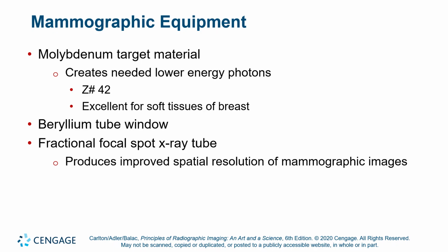Okay. If we use molybdenum as a target material, we're going to get lower energy X-ray photons out of a molybdenum target. Now, for X-rays of soft tissues like mammography, breast tissue, the molybdenum target is perfect for mammographic units. And so mammographic equipment has specialized X-ray tubes with different target material in the anode. They swap out the tungsten for molybdenum. They get a different characteristic X-ray of about 20 kVp or keV effectively. And they usually use a beryllium window.